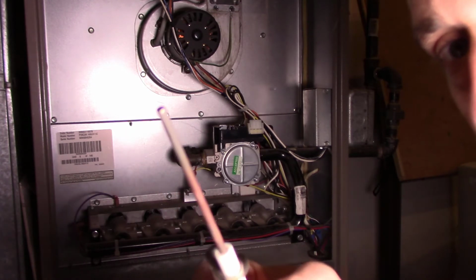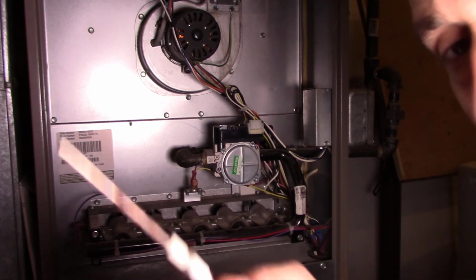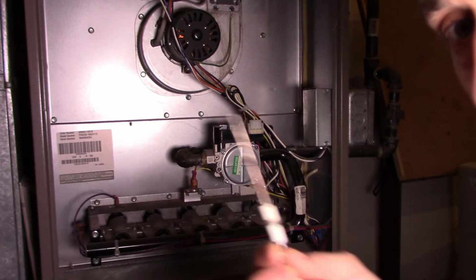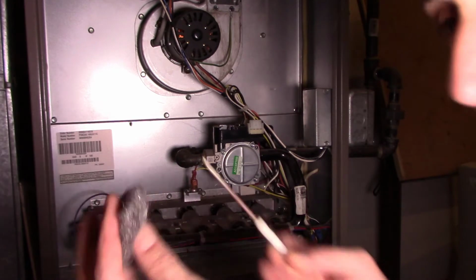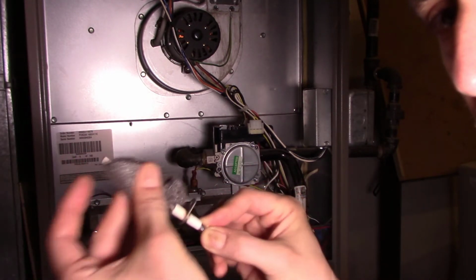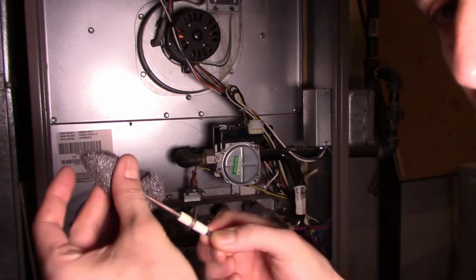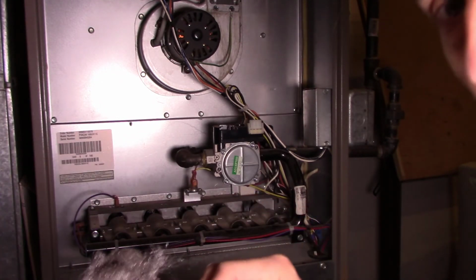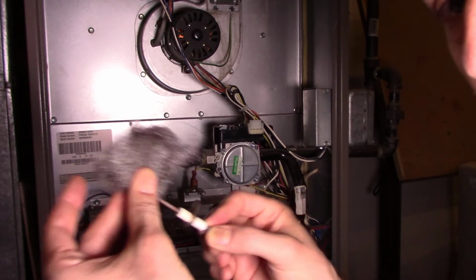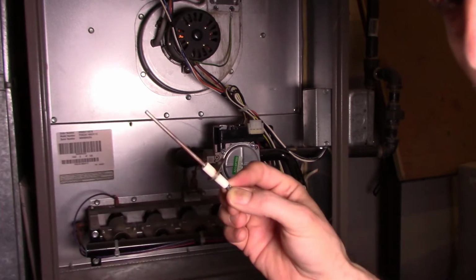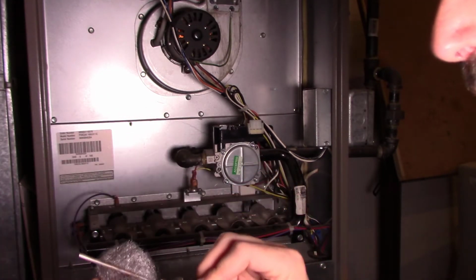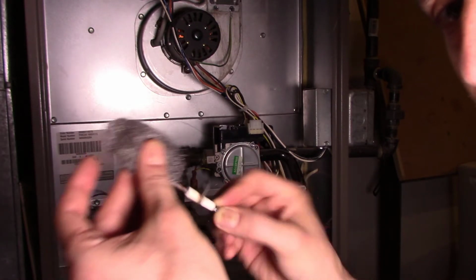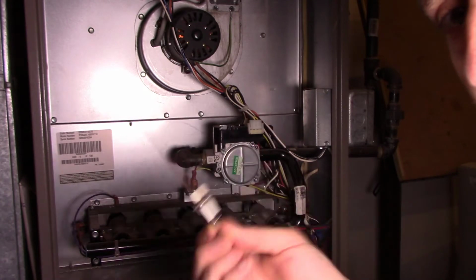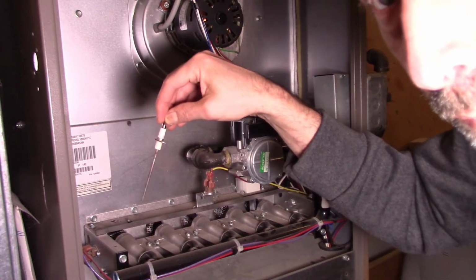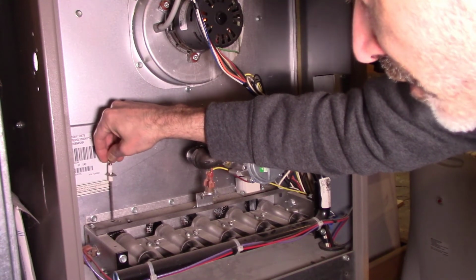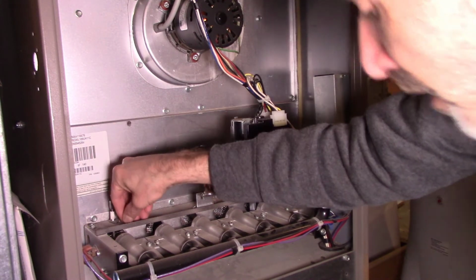Now, mine I keep clean every year. I do this as maintenance, just because it's so easy to do. The way to clean it is to take a little piece of mild steel wool and clean it. I've also heard techs, if you don't have steel wool in your kit, will take a $1 bill. Anything just mildly abrasive, no sandpaper, nothing with heavy abrasive, that'll ruin it. Something mildly abrasive like steel wool or even a $1 bill, and clean off any of the junk on it. That usually will take care of that problem. When you put it back, reinstall it carefully so you don't scratch it against the metal. Just carefully drop it back in there.